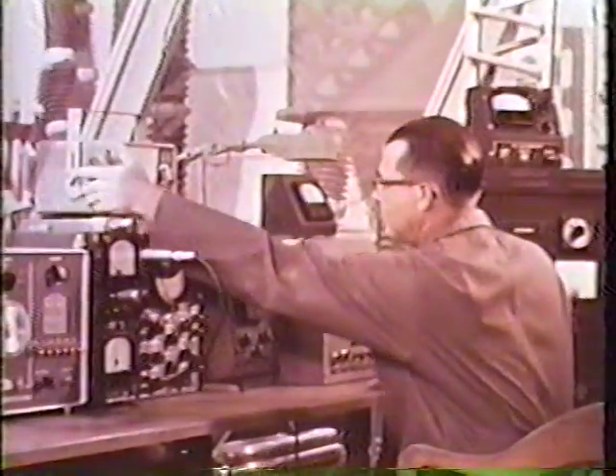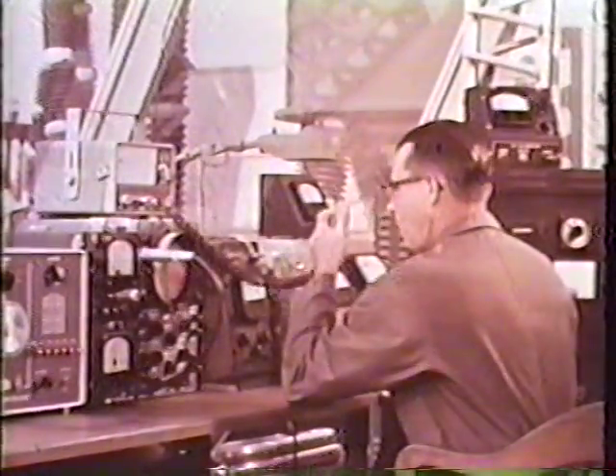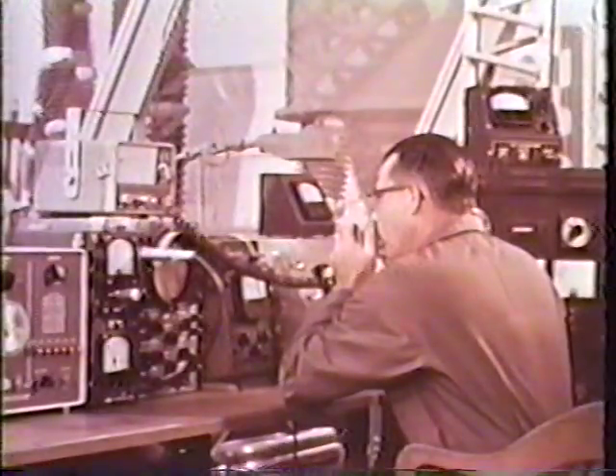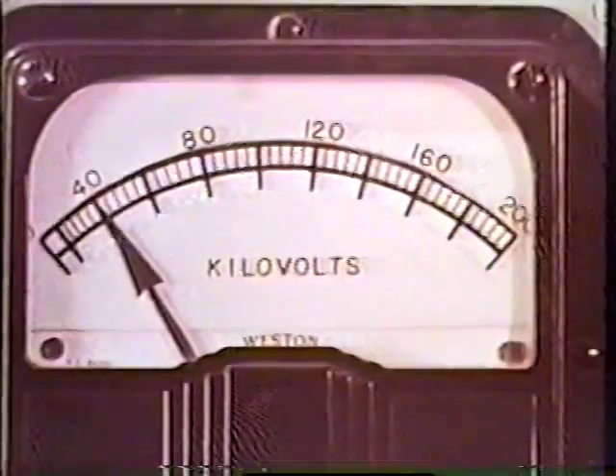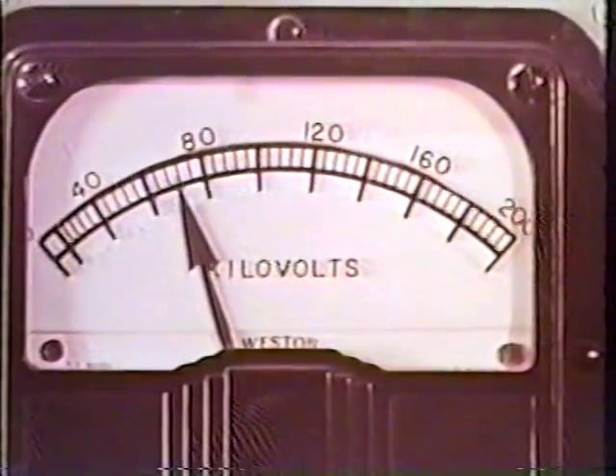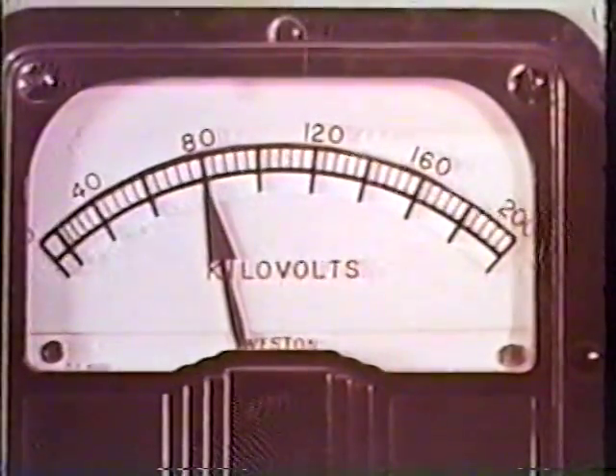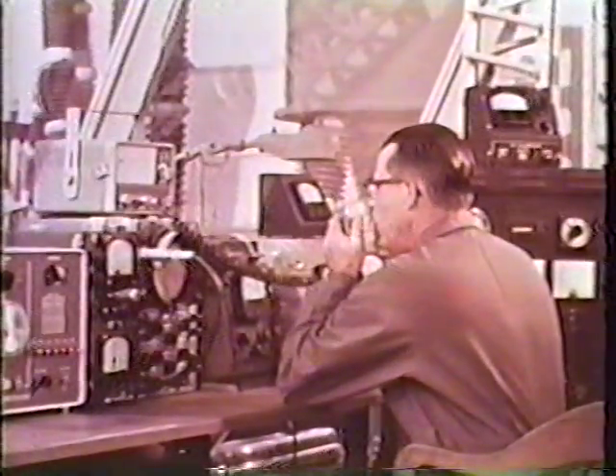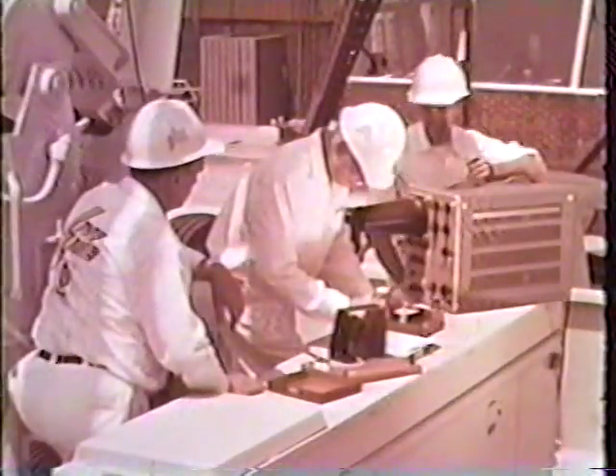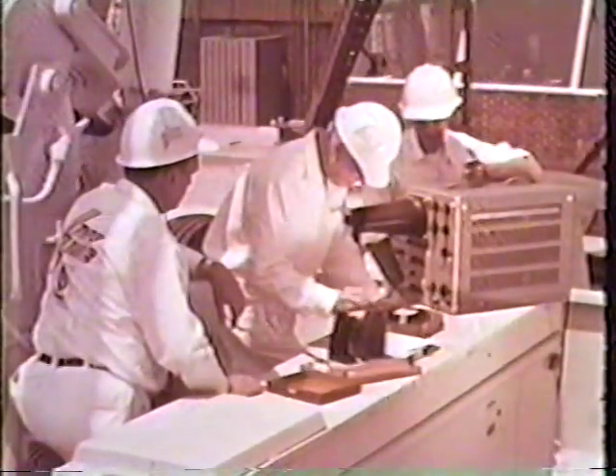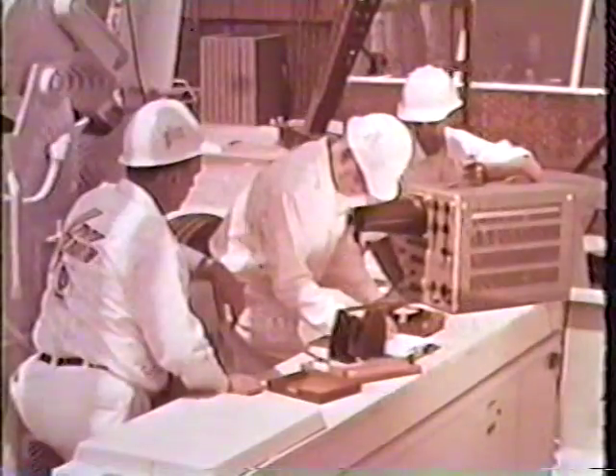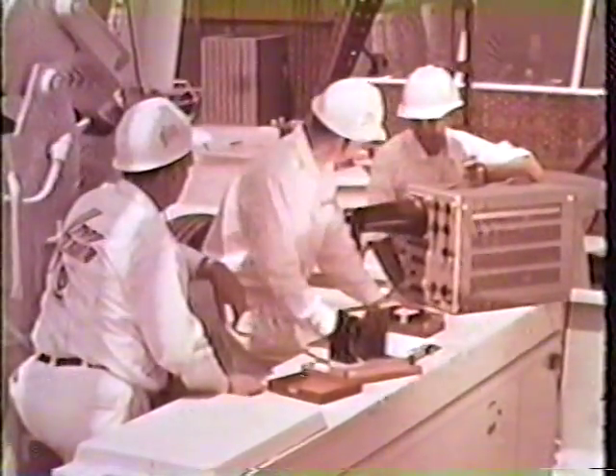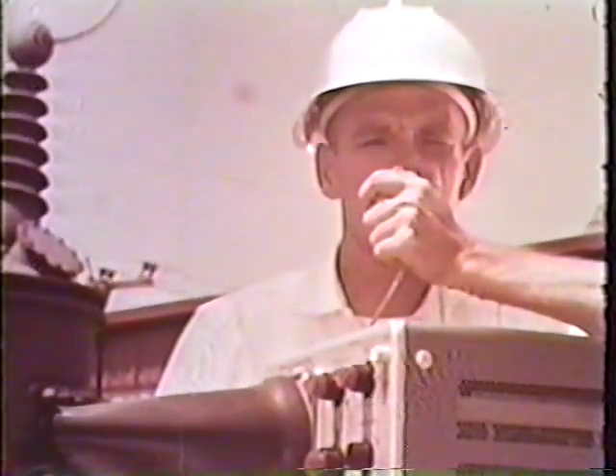After the bucket shielding has made contact, the conductor is energized at the rated voltage of the elbow. Since this unit is rated for use on a 138 kV system, it will be tested at 80 kV RMS to ground, the line-to-ground voltage of a 138 kV transmission line. The arm current at this voltage, normally around 70 microamperes, is recorded for the purchaser. This certified measurement thus becomes a benchmark for subsequent field tests.